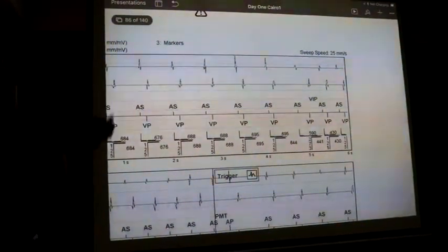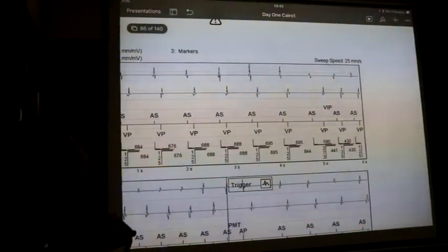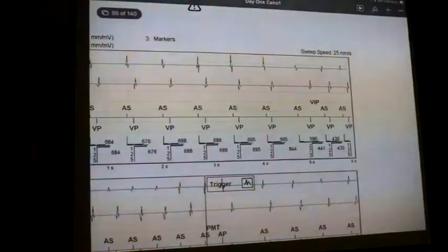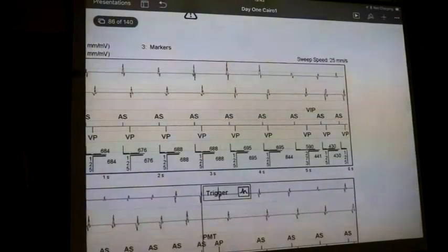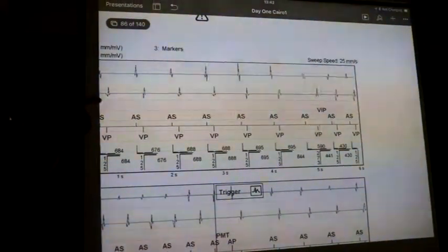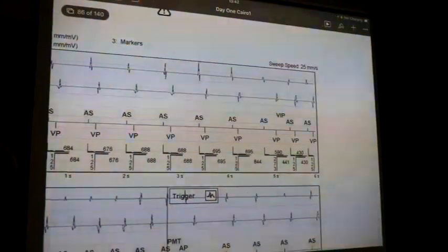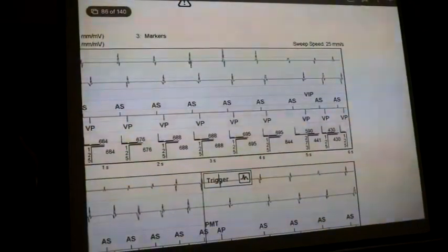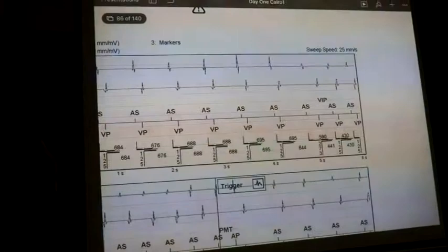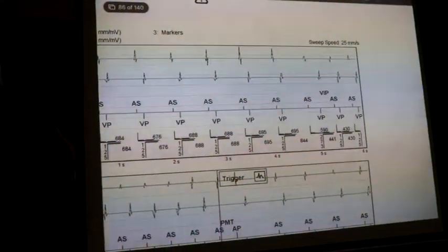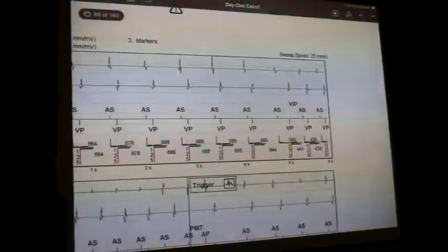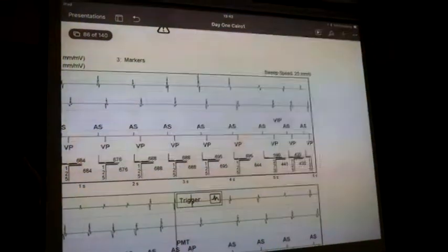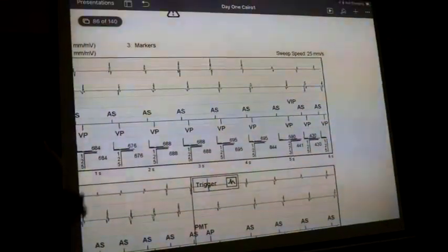It's done it once. Can you just turn it off or just decrease the extension of the delay? Absolutely. That would be what I would do. That's what we did with this patient. We decreased the extension, and we did a quick test to check whether this patient actually should be VIPing. Because this patient was getting kind of like 5% sensed activity. He's got AV block, right? Turn it off.